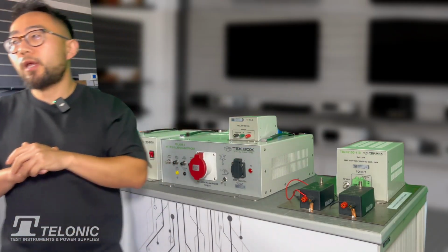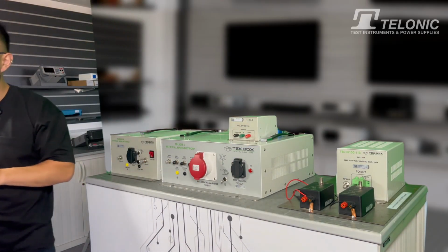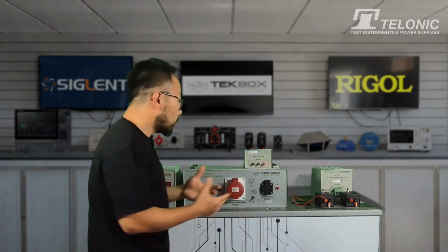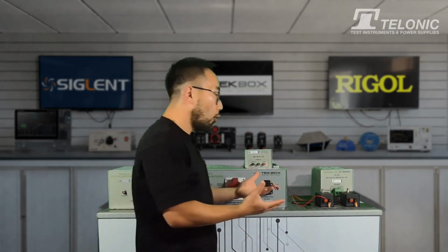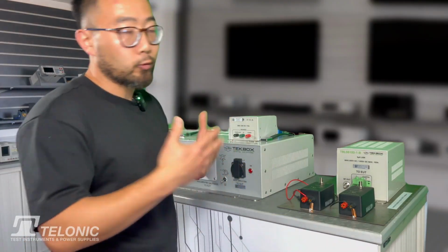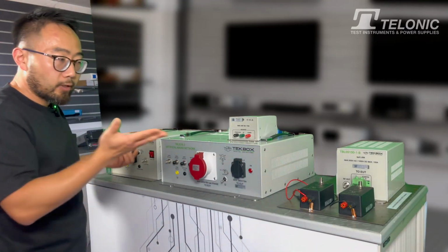Most of the DC LISNs are 5 microhenry inductance. And as you can guess, that represents the wiring harness impedance, often between the distribution box and the voltage source. Typically that is a battery, 28 volts, 24 volts or 12 volts, depending on the application. So that's the DC types of LISN. Very similar to AC, either on the 28 volts or 0 volts or 12 volts or 0 volts, you must always terminate the other port that you don't measure with a 50 ohm terminating resistor.